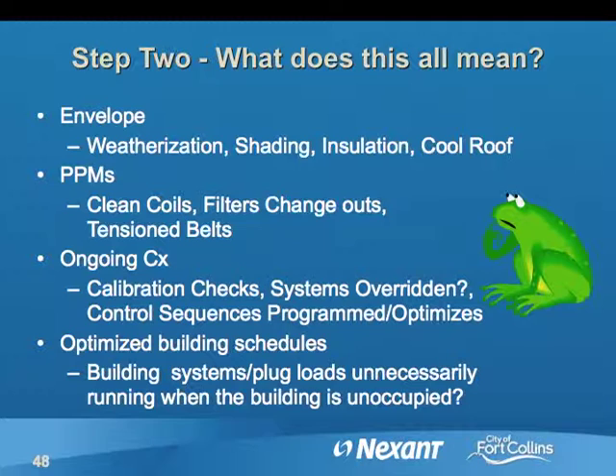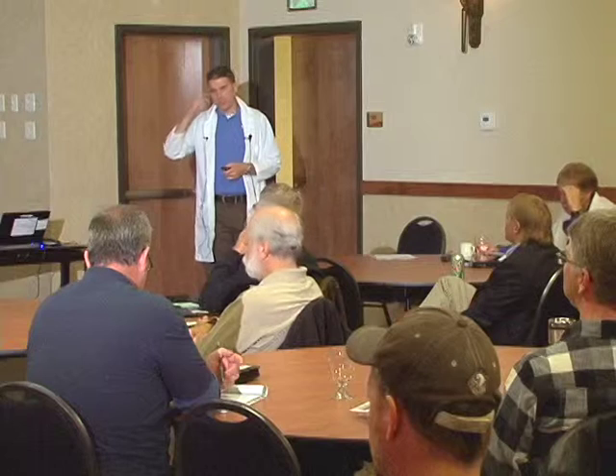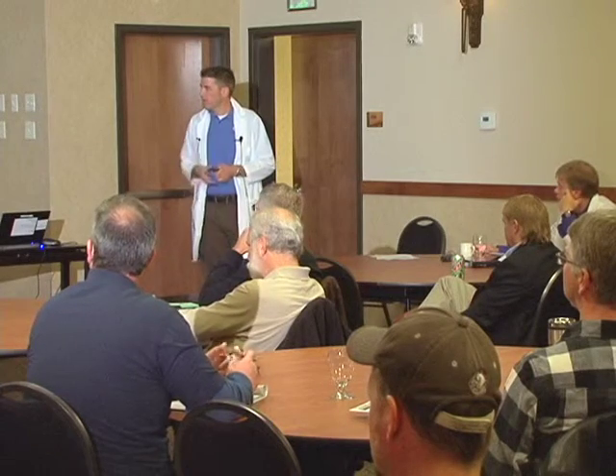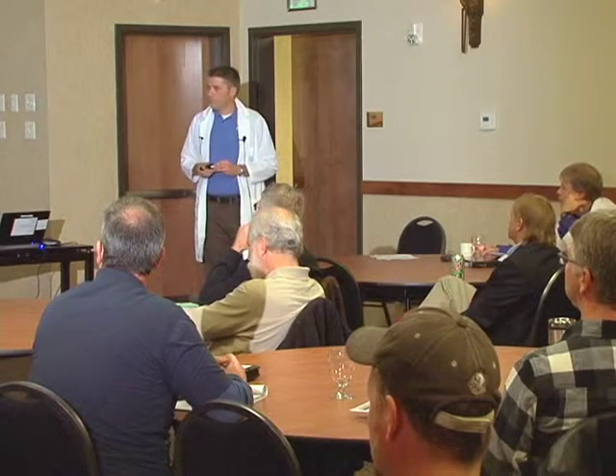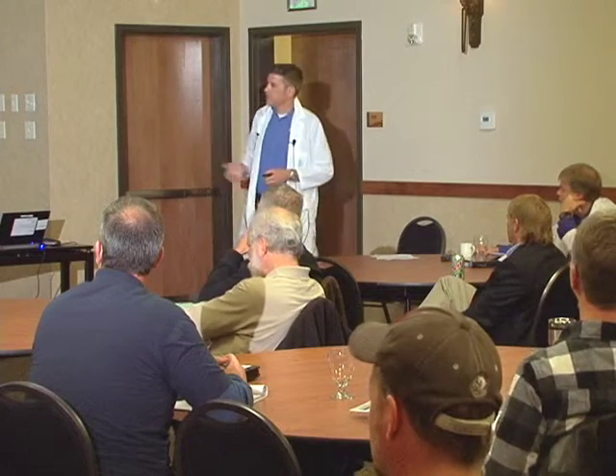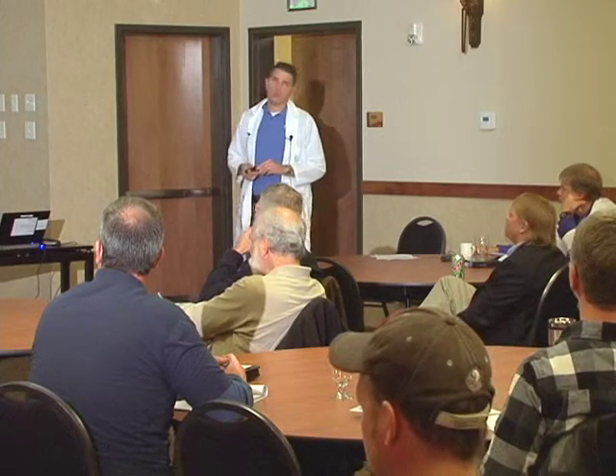Ongoing commissioning. That's where we talked about calibration checks. If you have a much bigger building, are we making sure that the outside air damper is still functioning, year in and year out? Those things do eventually break, or they freeze up, or they rust. And of course, if you have a damper that's rusted 100% open, that could be a big energy user. Or the system's overridden.